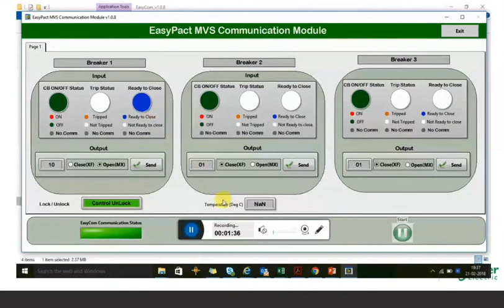I will give a command to the breaker so you will understand how easy it is to operate. It requires a password. Once you have the password, you can generate a command for the breaker. Once the command is generated, you can see the breaker status has changed. Now the breaker is on. Again I am giving a second command to open the breaker. Once the command is executed, you can see the breaker is off and still not ready to close. It will wait, charge the motor mechanism, and then be ready to close again for the second operation.